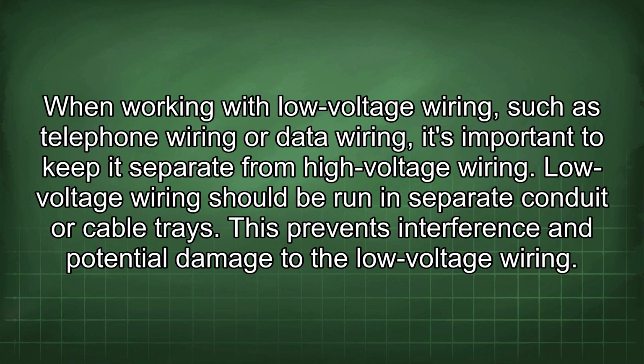When working with low-voltage wiring, such as telephone wiring or data wiring, it's important to keep it separate from high-voltage wiring. Low-voltage wiring should be run in separate conduit or cable trays. This prevents interference and potential damage to the low-voltage wiring.